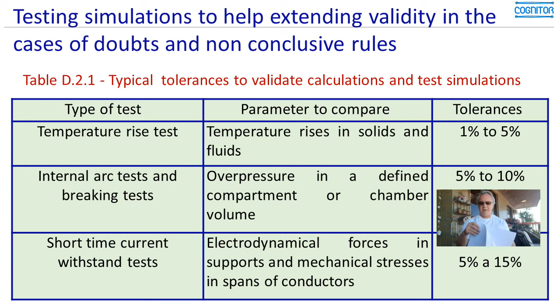For example, you do tests on one equipment that presents one certain temperature rise in certain parts, and you can simulate this very well with a very small error. Then you do a modification in one fuse link or in one conductor, one small modification, and you do the same simulation for this other equipment. Why not believe that the result will be acceptable? It would occur in a real test. We define here certain values of tolerance to do this.